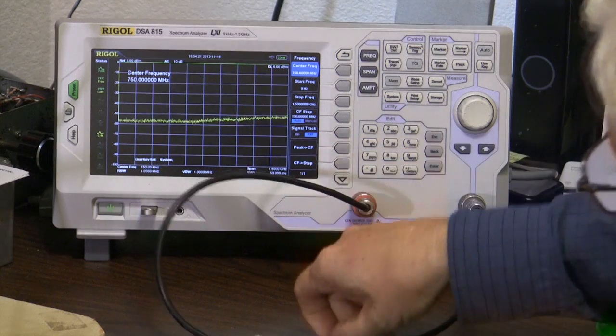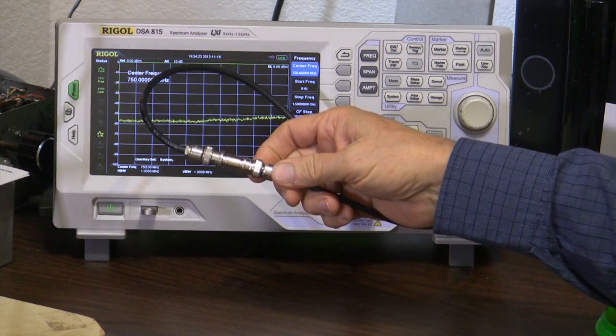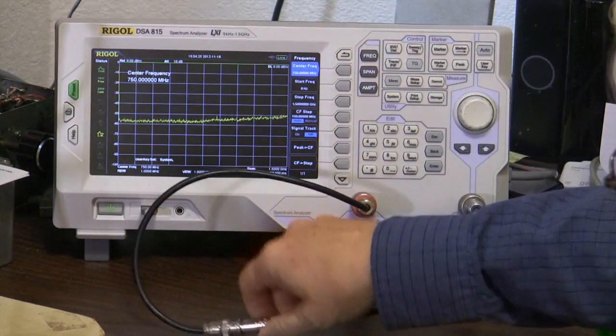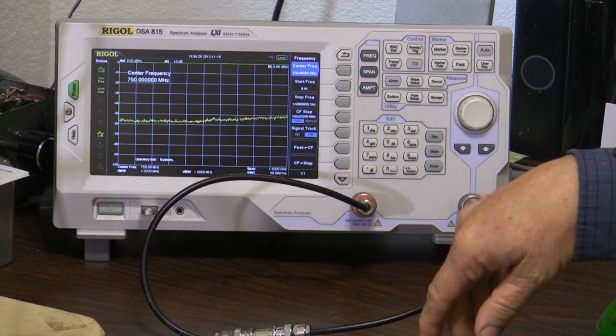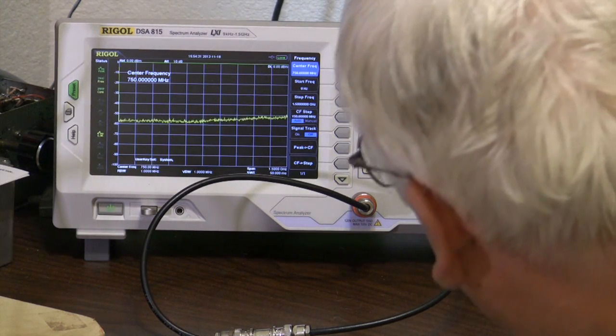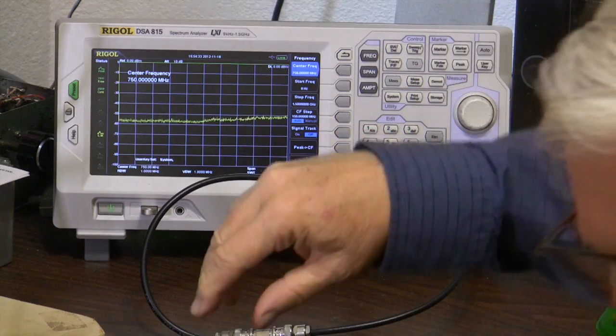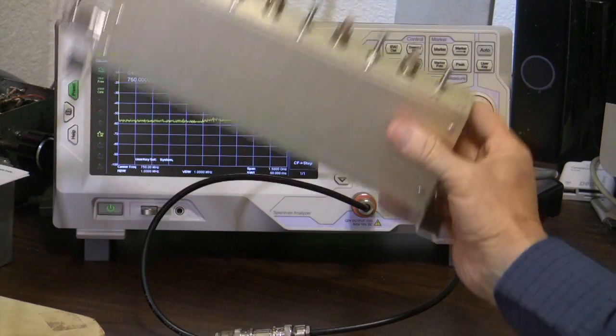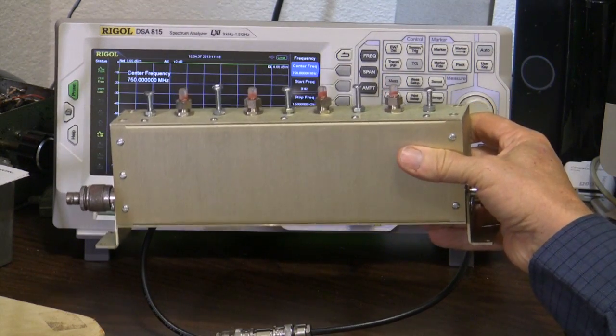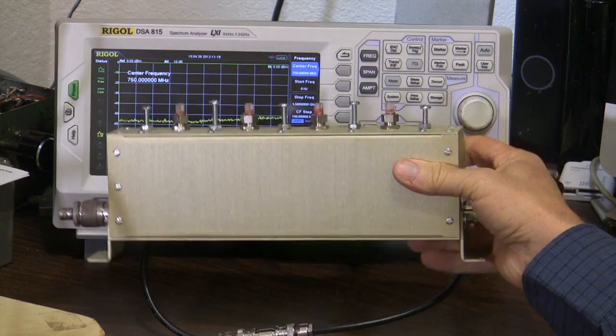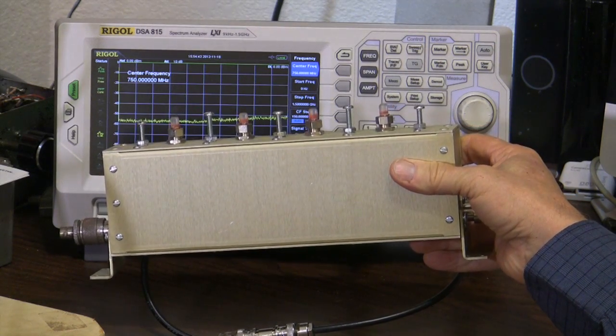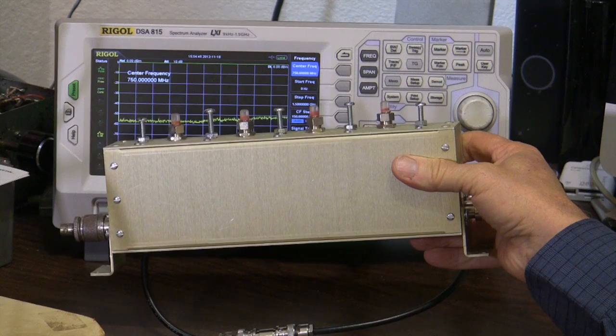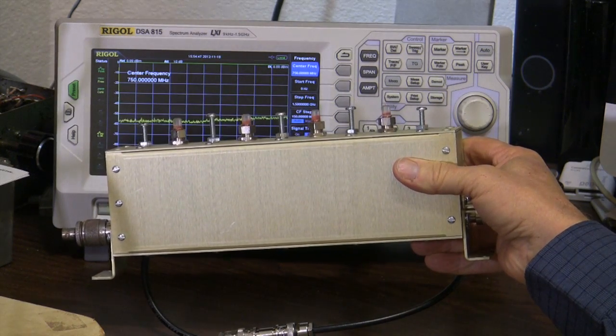We start out by doing our usual and setting up a cable from the tracking generator to the spectrum analyzer input. And first thing I'm going to do, I know for a fact that this is at 169 plus or minus megahertz.